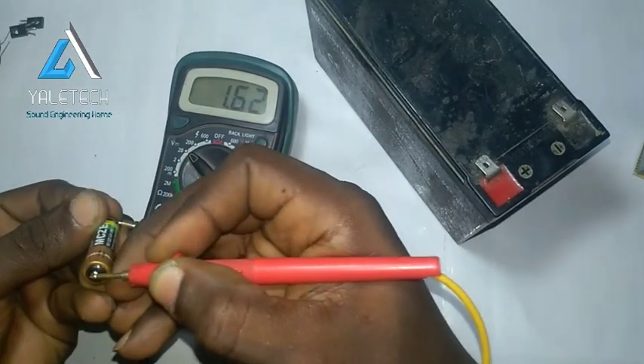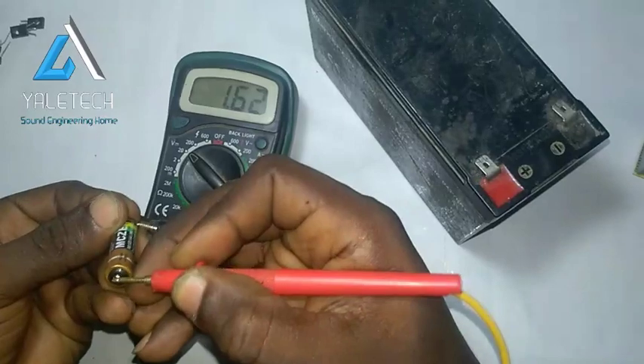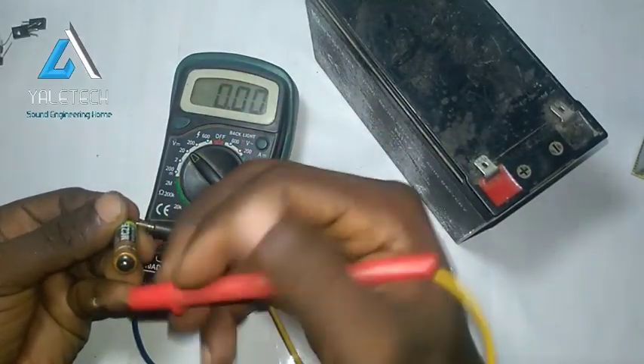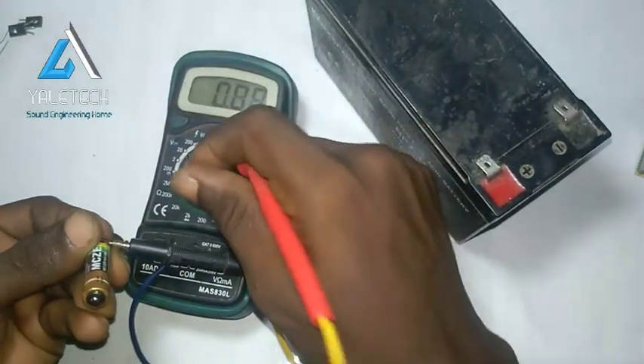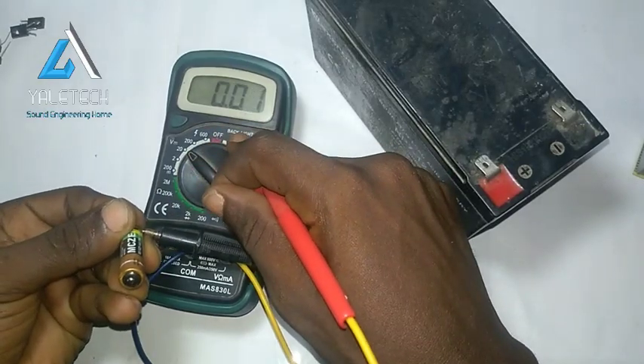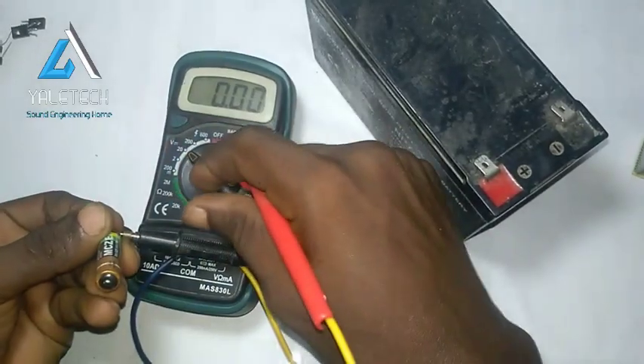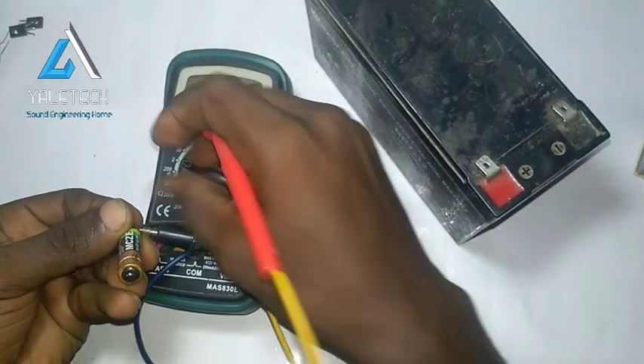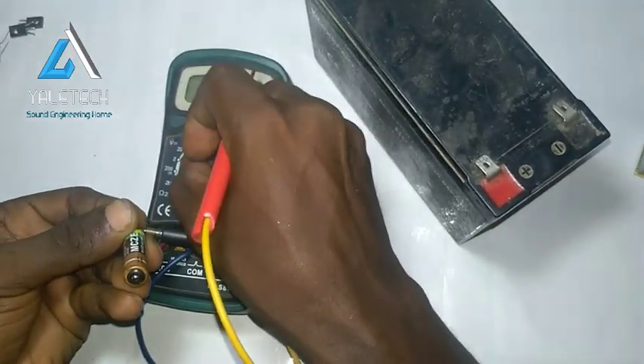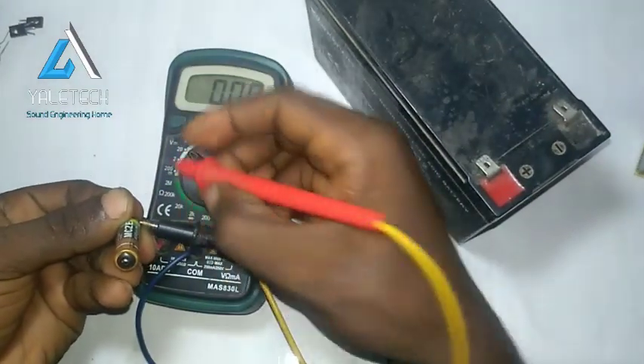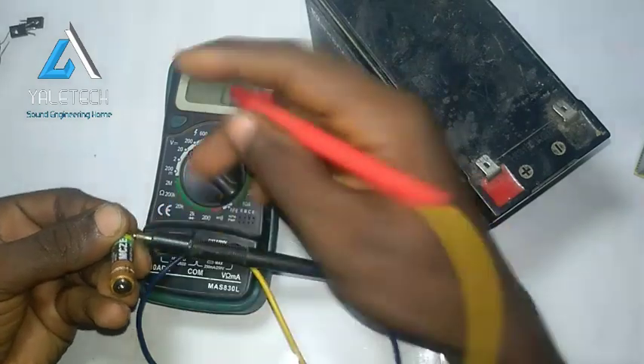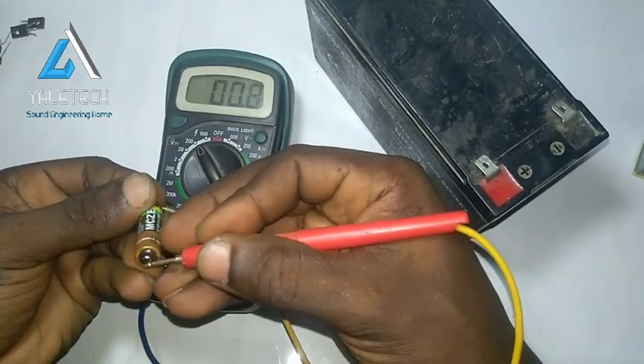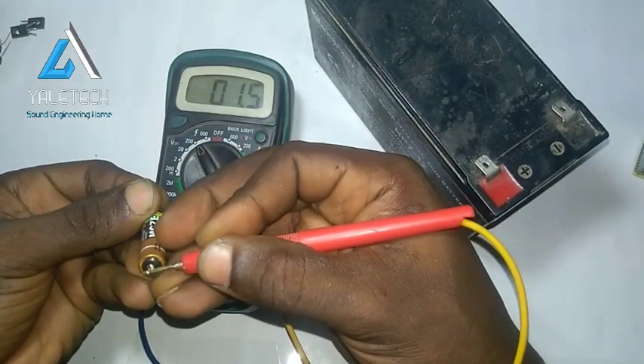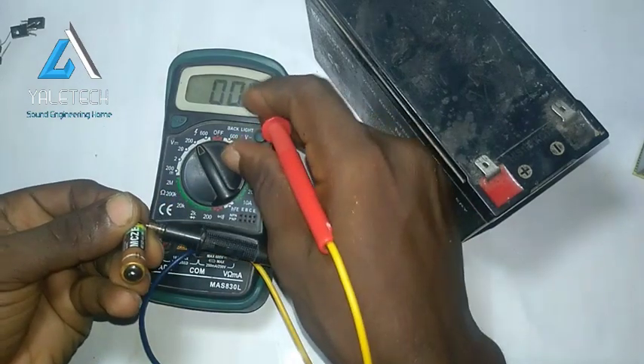It's better to have more allowance space. It's better that the voltage is lower than the rating you are choosing, rather than the voltage being more than your rating. If I'm testing 200 and put it at 2, I will spoil this. But I want to test 1.5, even though I use 20, it's still okay. If I switch it to 200, let's see, it's still figuring out, still 1.5.